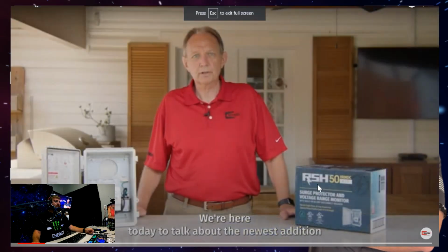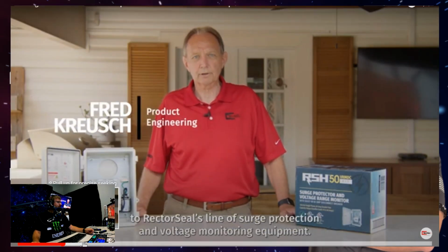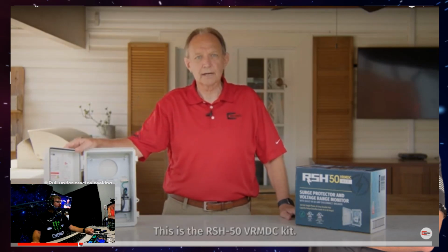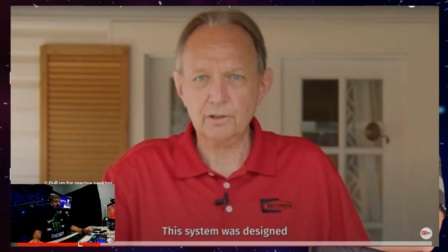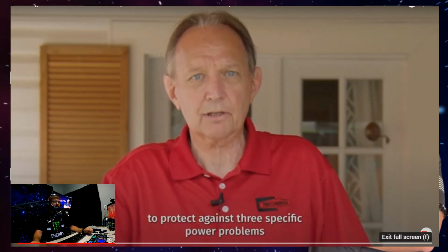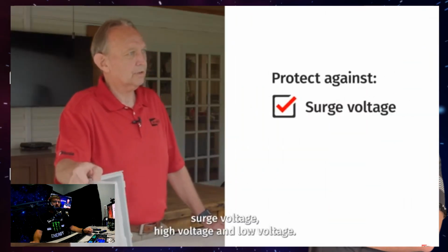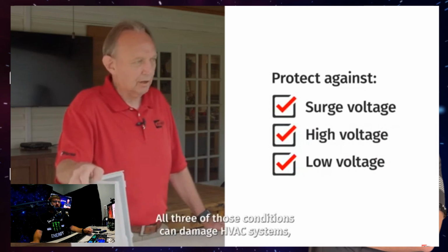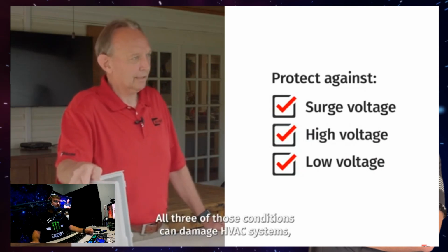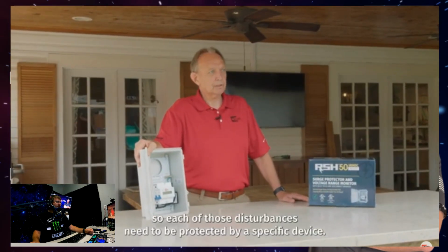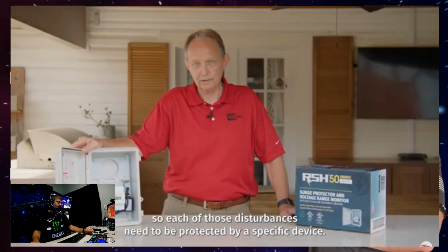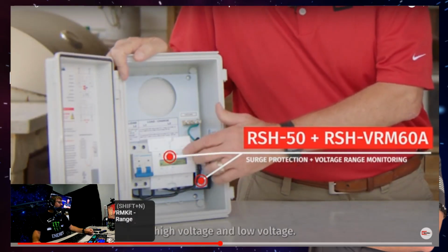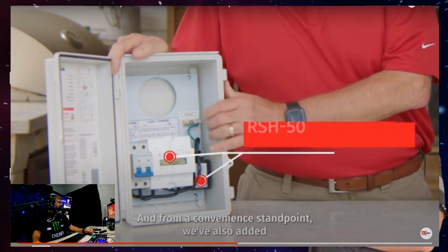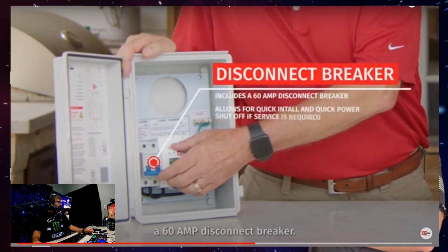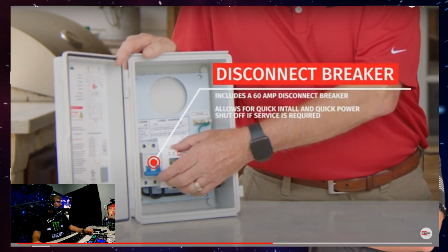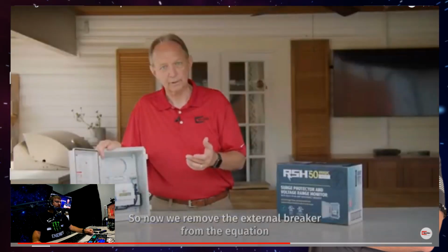We're here today to talk about the newest addition to RectorSeal's line of surge protection and voltage monitoring equipment. This is the RSH50 VRM DC. Not a sales pitch. This system was designed to protect against three specific power problems: surge voltage, high voltage, and low voltage. All three of those conditions can damage HVAC systems. So each of those disturbances need to be protected by a specific device. So you have surge voltage, high voltage, and low voltage. And from a convenience standpoint, we've also added a 60 amp disconnect breaker. So now we remove the external breaker from the equation.